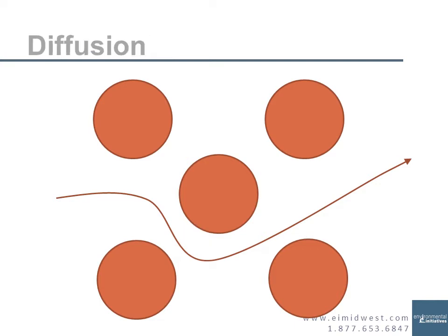Diffusion is what happens with really small particles. Particles that are really small will follow the airstream, but they are vibrating, and they're very erratic. It's called Brownian motion, so they're kind of all over the board. And then finally, because of Brownian motion and them randomly zigzagging, they zigzag accidentally right into the filter fiber.